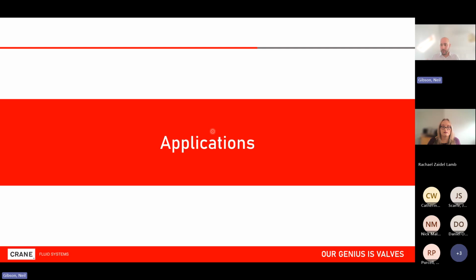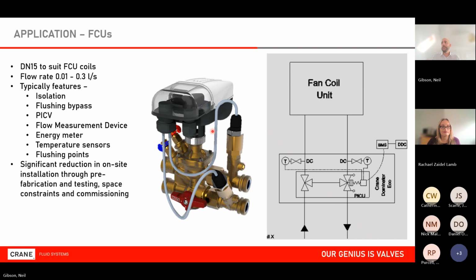Let's look at some quick applications, conscious of time, and then leave enough time if there's any queries at the end. It doesn't have to be huge, bulky, and expensive. So we can use these types of solutions on devices as small as 15 mil fan coil units. I'm using fan coil unit as an example here. And I don't have to have huge ultrasonic flow meters, for example. I don't have to have huge rotary control valves. In reality, what I want is a system that can control flow rate while monitoring delta T to generate this power. And you can see an example here.